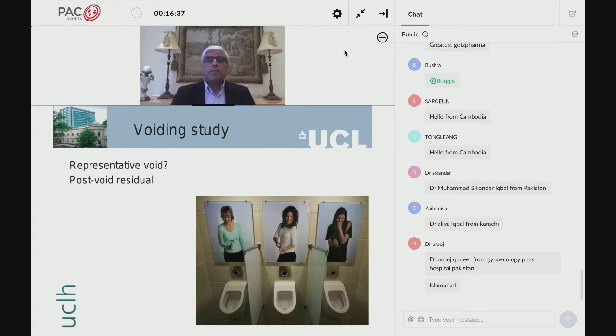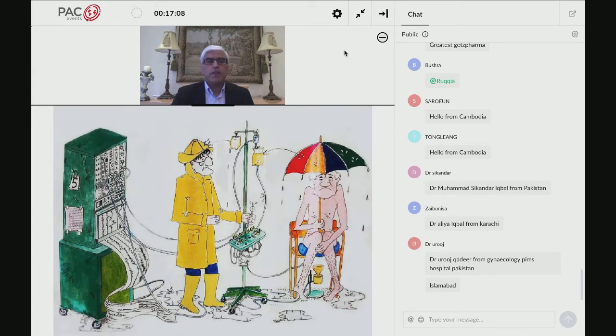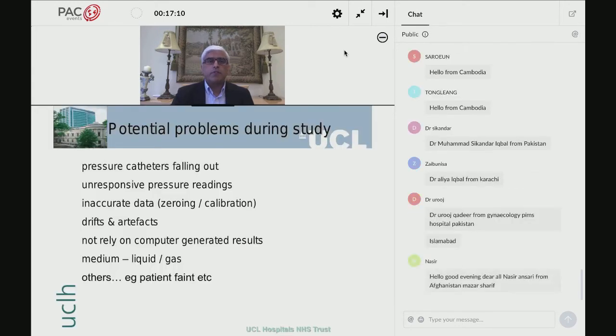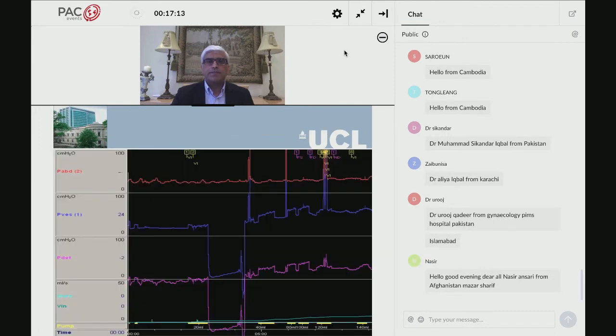Catheters can fall out, the readings can be unresponsive, the data is not accurate because the zeroing has not been done, or the calibration has not been proper. There can be drifts or artifacts. Urodynamics is one of the things where one must not rely on computers. And there can be other problems, whether you're using liquid or gas, and it has happened to all of us. Then some of the patients might faint as vasovagal. In non-neurogenic patients or in neurogenic patients, one needs to be aware of autonomic dysreflexia in patients who have an injury above the level of T6.